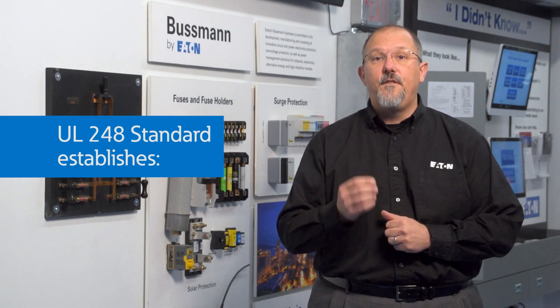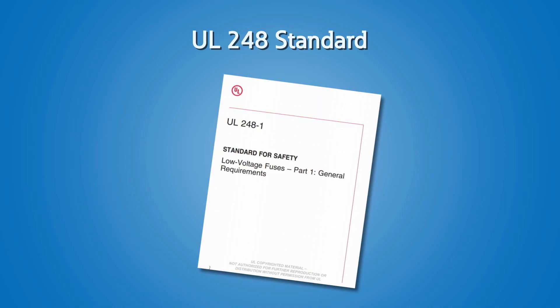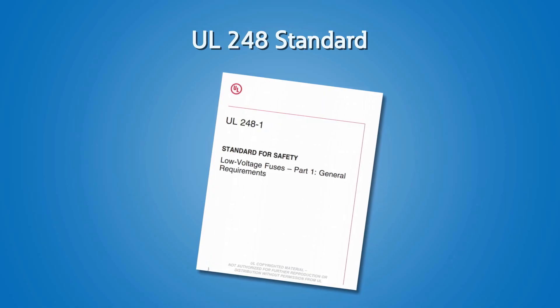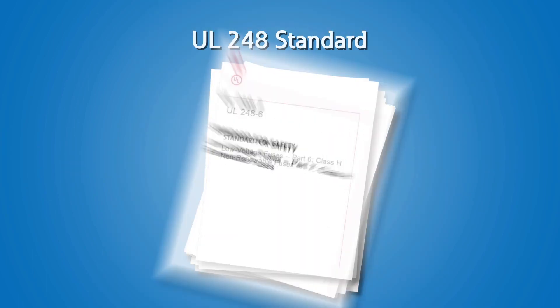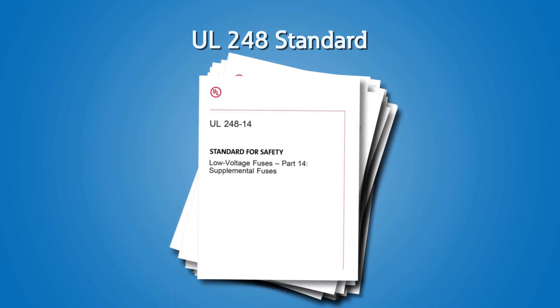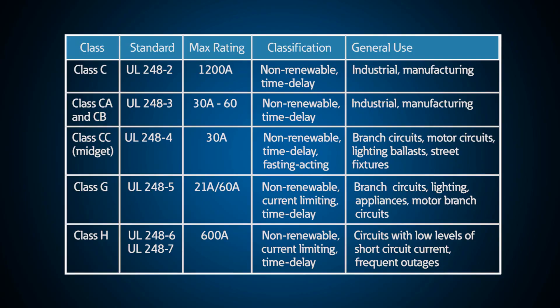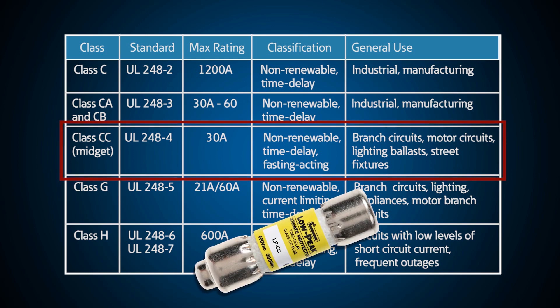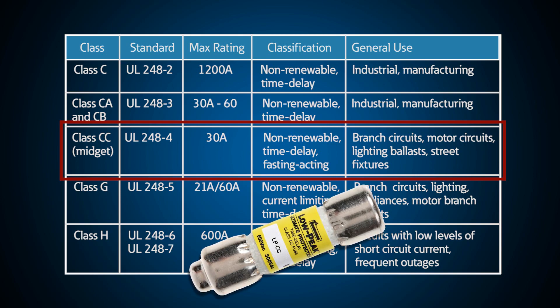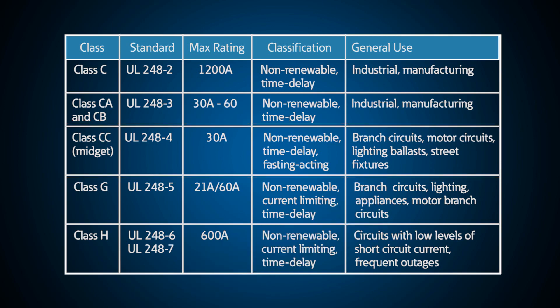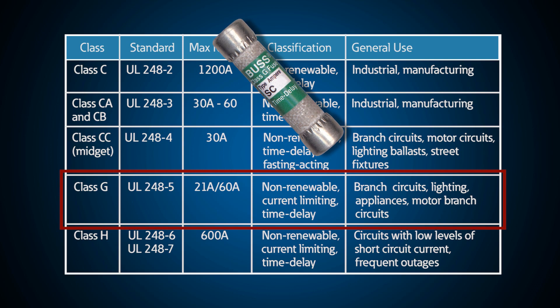UL248-1 covers general requirements. Beyond that, additional documents identify all the various fuse types, each with a purpose in the power distribution system — from a circuit board in your computer to a utility transformer outside your building. Class CC fuses, listed to UL248-4, are small fast-acting fuses for protection of branch circuits, motor circuits, lighting ballasts, and street light fixtures.